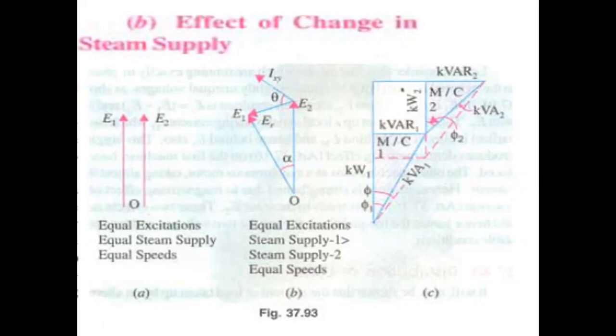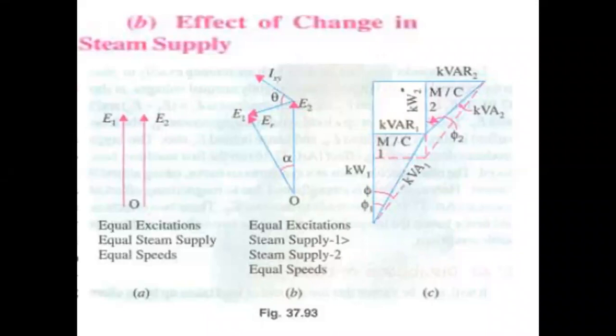The power per phase for machine 1 is increased by E1 into ISY. The power for machine 2 will be decreased by the same amount — if you increase alternator 1 power by 10 watts, the same 10 watts is decreased in alternator 2. ISY is a reactive component; increasing steam supply only increases the active power output of alternator 1 and decreases the active power output of alternator 2.